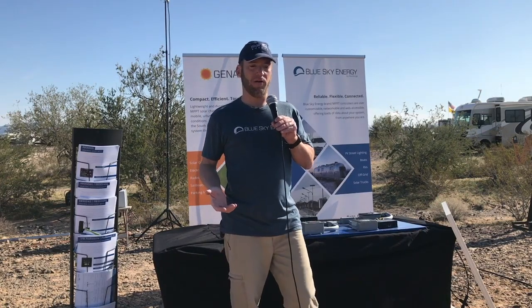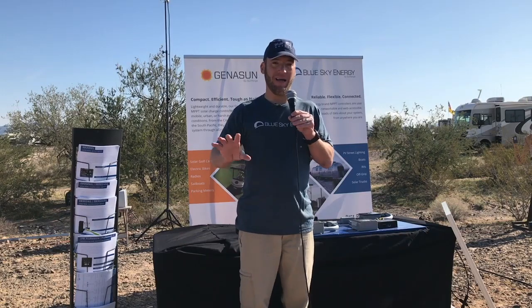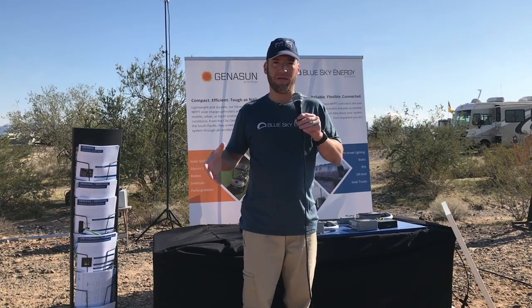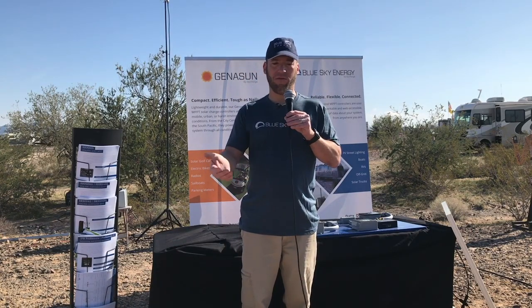Yeah, I agree. He was asking or making the comment that lithium batteries are lighter. Ooh, they're a lot lighter. We're talking about a quarter to a third of the weight of a lead acid battery, so I completely agree with that. They also have higher energy density. If you look at the form factor, most of them do have higher density, but it depends on the enclosure they use. For example, if you're keeping one battery underneath your step, and that's the only place you can put batteries, you're going to get away with more amp hours underneath that step with a lithium battery. Also, like I mentioned, if you have a 100 amp hour lithium, you've got about 80 to 90 to work with before you're on the tail end of the hockey stick. If you've got a 100 amp hour lead acid battery, you've got about 60, 65 to work with before you start damaging it. So not only is it more compact as far as energy density, you get to utilize more amp hours out of it - you have more energy, more power in there to use.